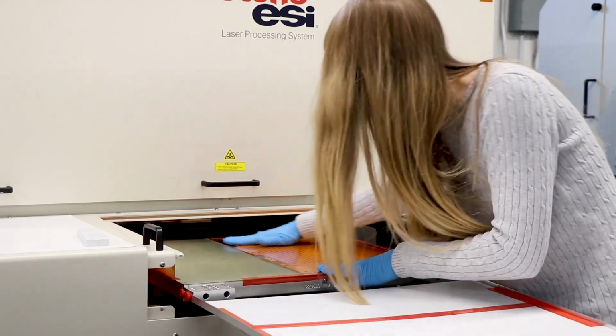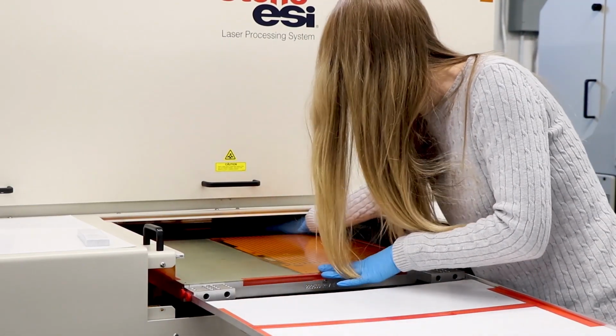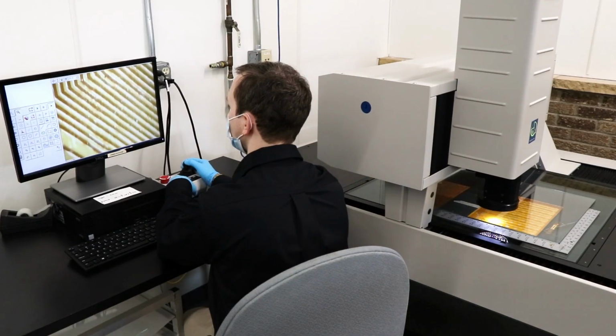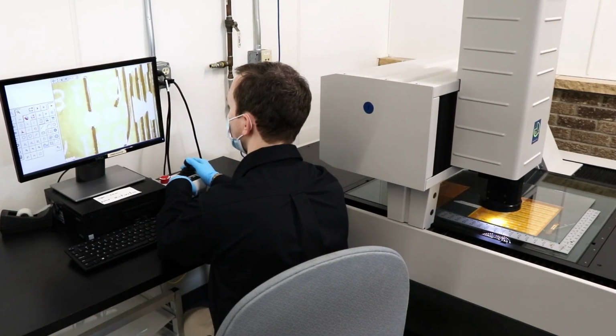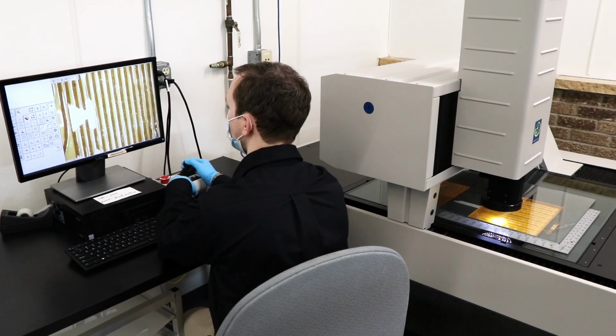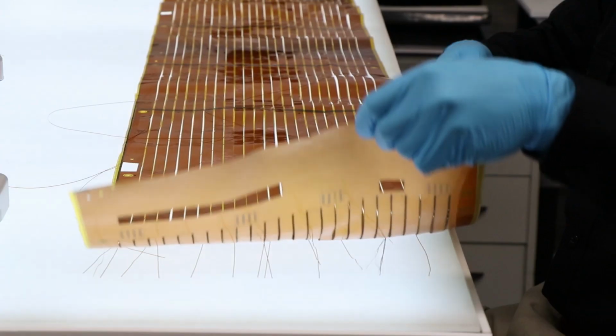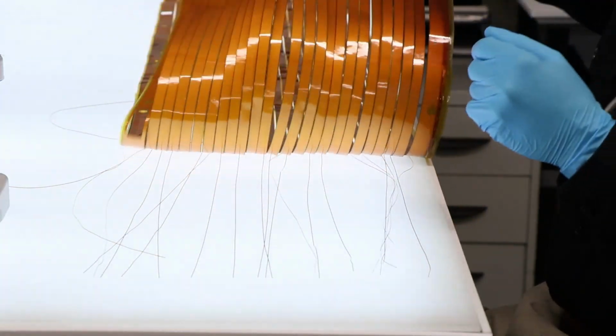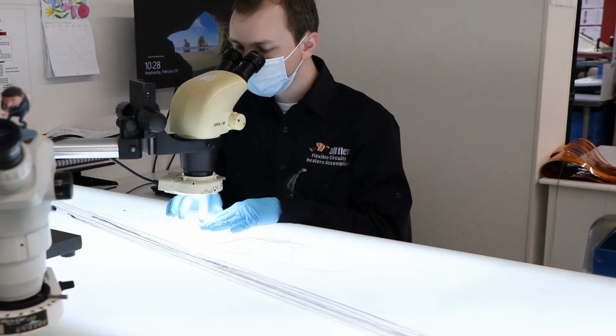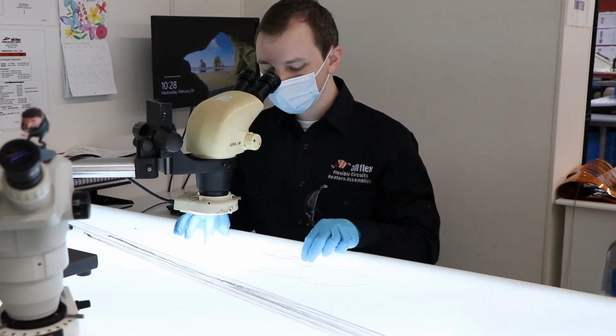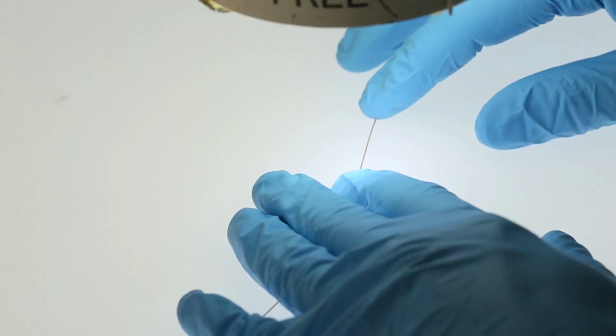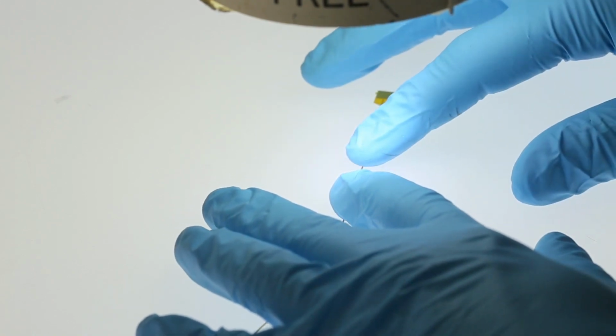CatheterFlex circuits are an extended length circuit that are custom designed to reduce your assembly time and increase spacing by replacing traditional lead wires. We build various products from single-sided and up to 8 conductive layers in one single flex. These circuits can range in length from 24 inches to in excess of 100 inches, with a conductive trace and spacing down to 2 mils or 50 microns in width.